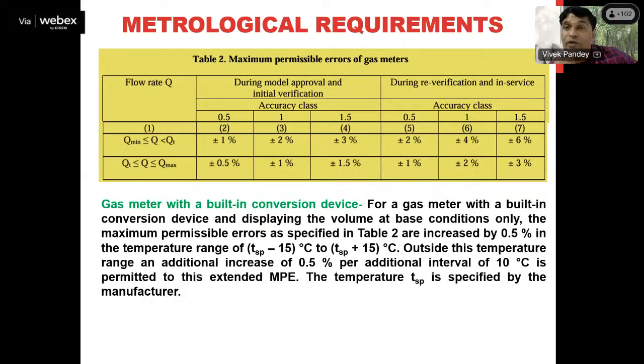Okay, so during re-verification and in-service inspection, the tolerance will get doubled. So plus minus 2% between Q minimum to QT, and plus minus 1% for accuracy class 0.5. Now here one more thing is to be considered, and that is what?